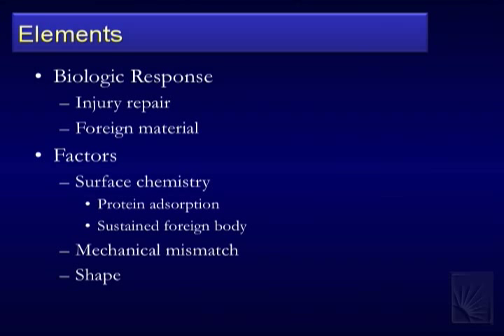I also have to address surface chemistry: how do I keep proteins off the device, keep it from fouling and causing a continuous response? Protein adsorption leads to a sustained foreign body reaction. Then mechanical mismatch — which I think is very important — and shape: at this size scale, devices are on the same scale as axons, and neurons interact with things that have shapes and material properties they like or dislike. Different stiffnesses cause different cell interactions. All these things become very important at the nanoscale.